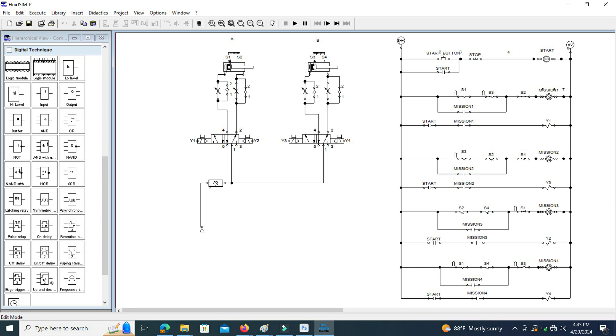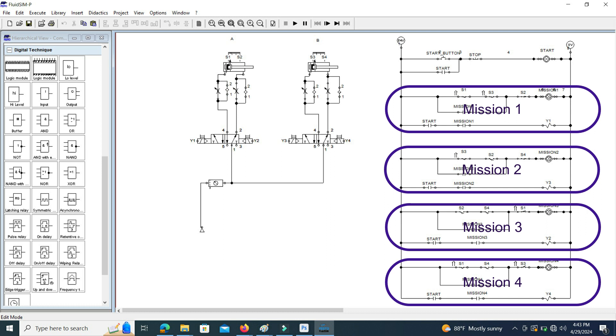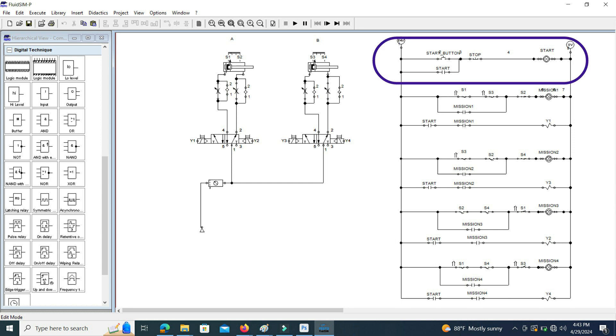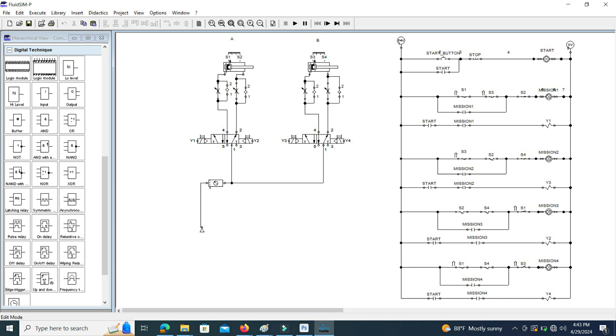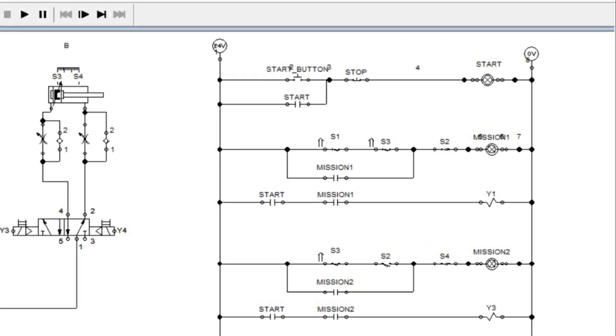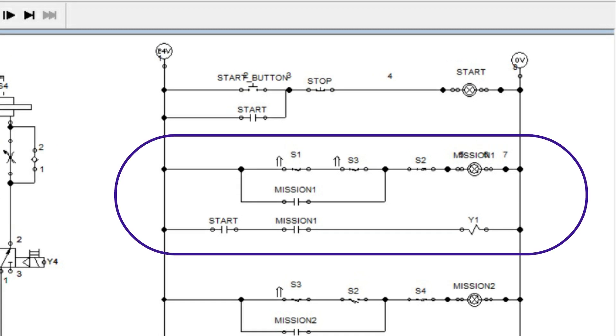Here you can see the ladder logic program designed for this operation. It uses a mission sequence structure, where each task is considered as a mission. First, you can see the start latch — it latches the start memory when the start button is pressed, and resets when the stop button is pressed. Initially, both cylinders are in the retracted position, with S1 and S3 signals high, and S2 and S4 signals low.